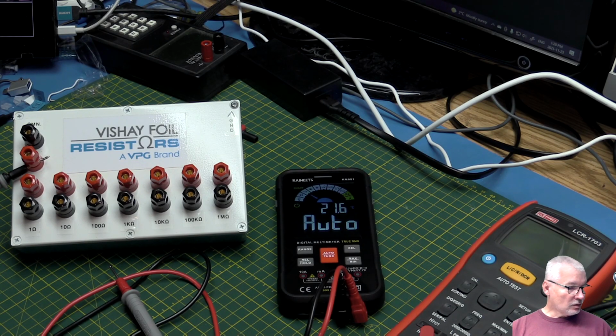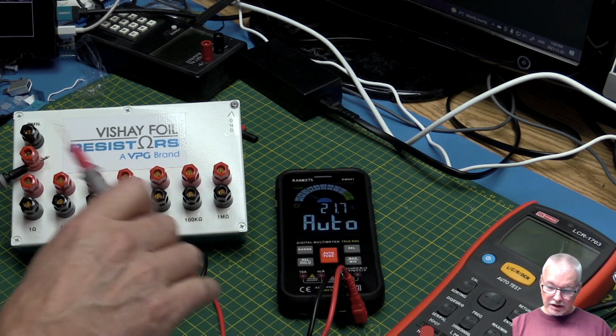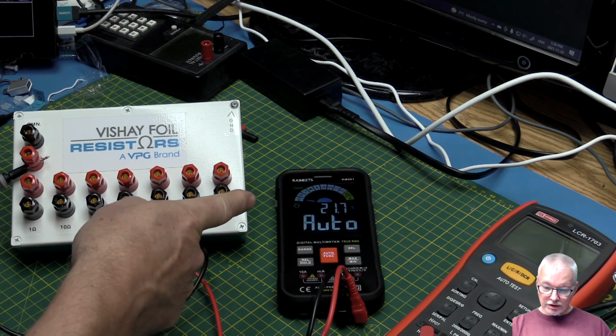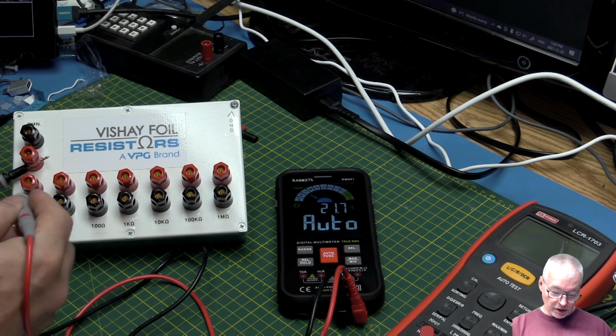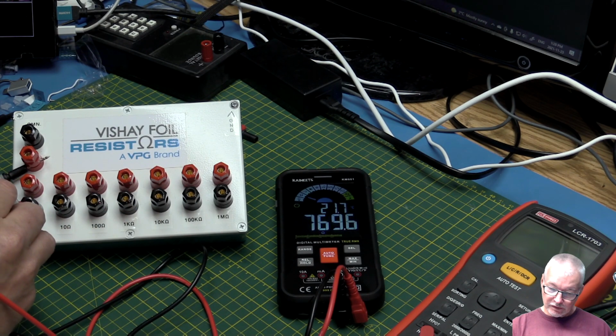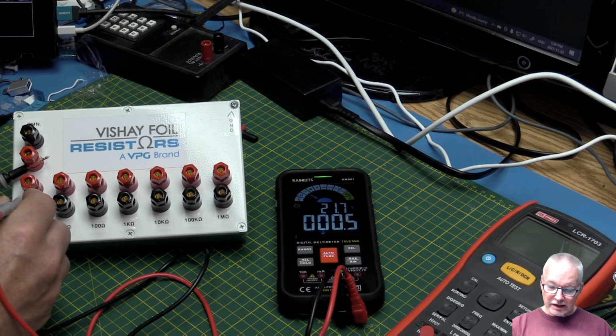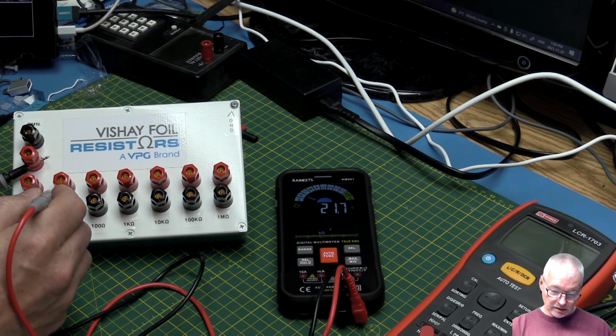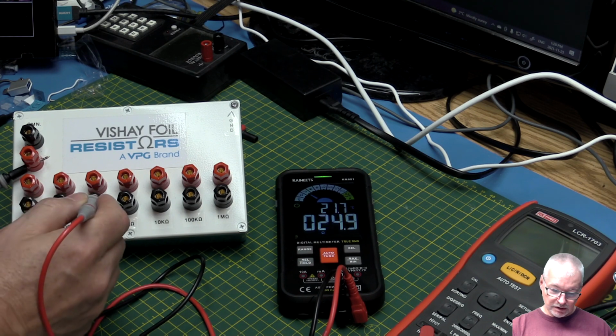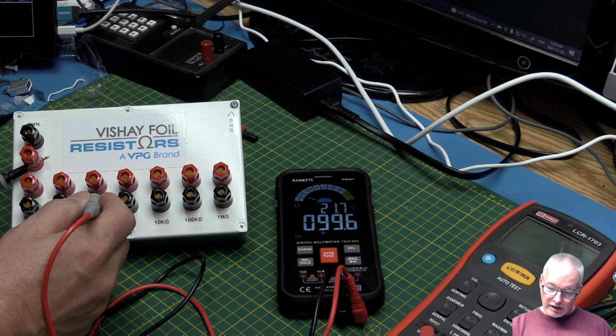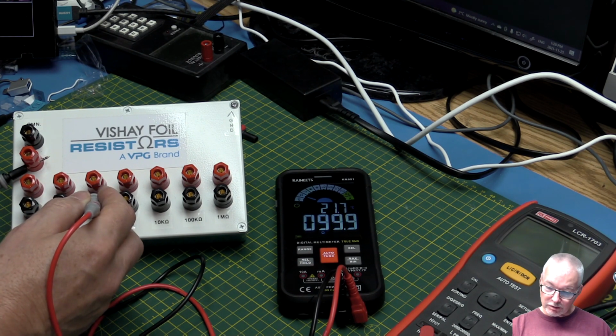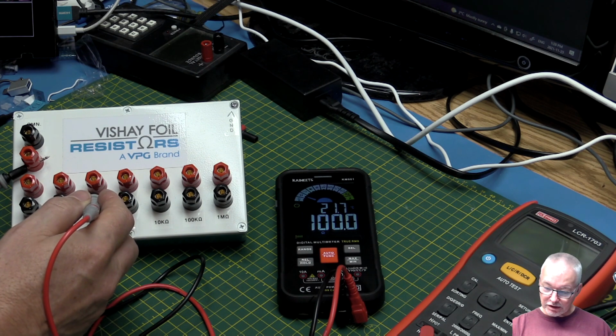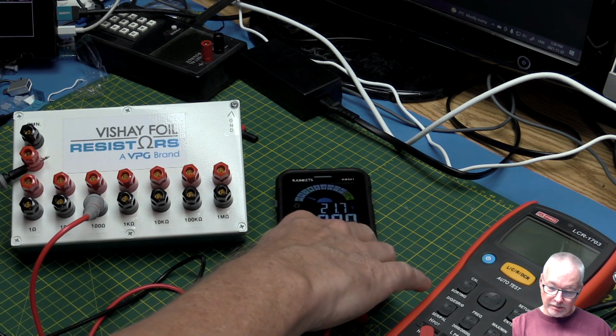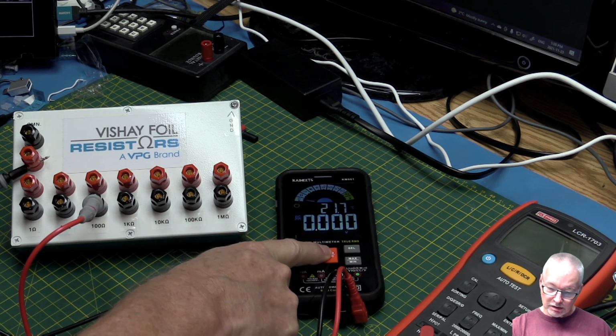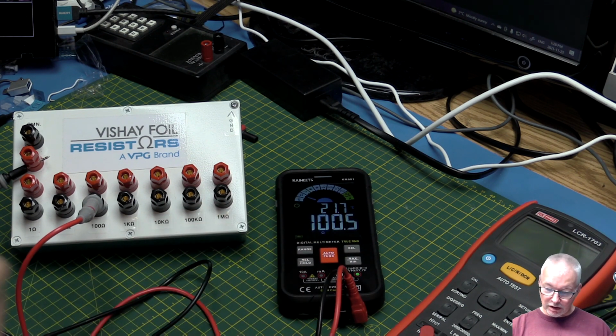Alright, so we're looking at the resistance standard. I've got the meter plugged in. The first thing to check is on auto, which range is it going to choose when I give it a 1 ohm resistor? Looks like it's locking into continuity. At what point does it think it's a resistor versus continuity? There you go. As soon as you give it something 100 ohms or more, it gets into resistance mode. So I'm going to set it permanently into resistance mode, just so that we can measure the lower ends.